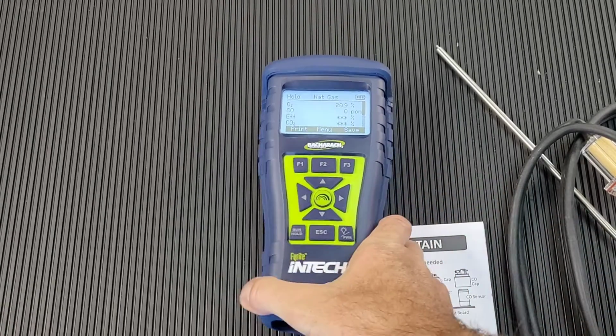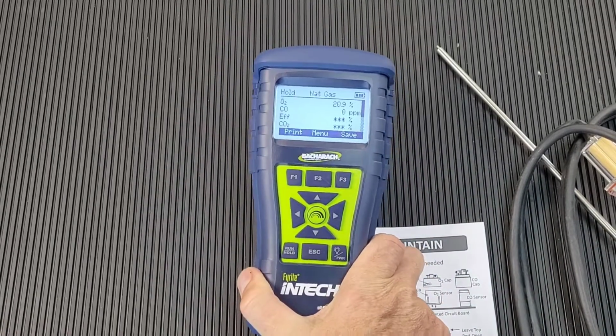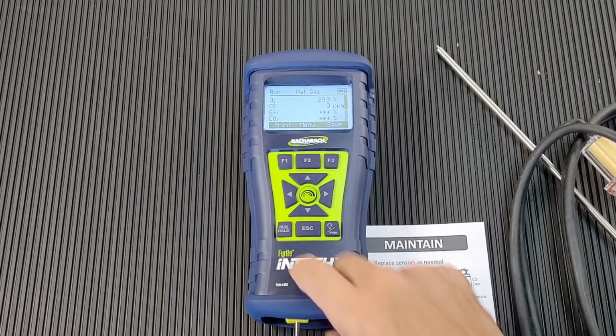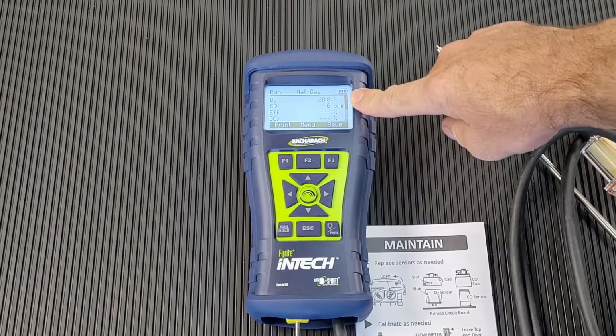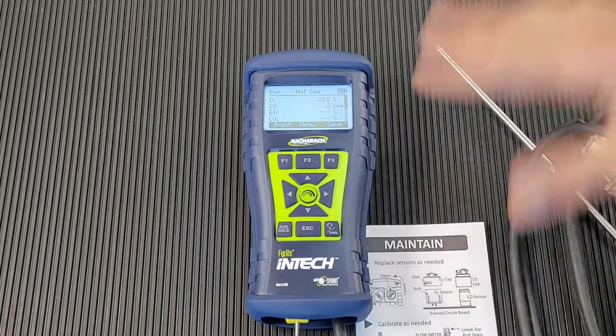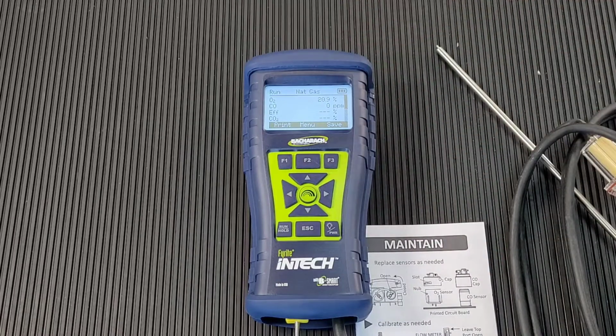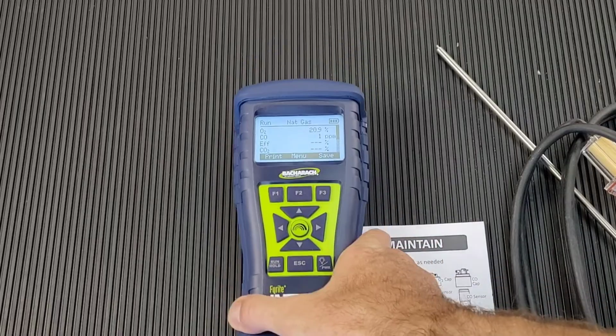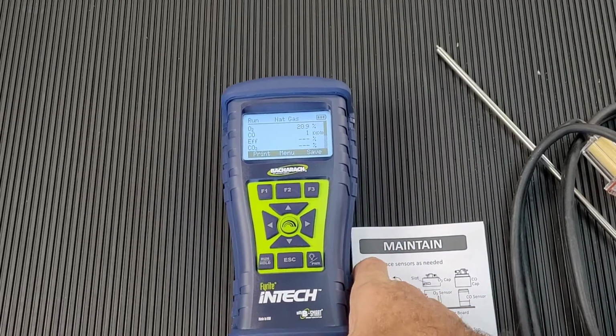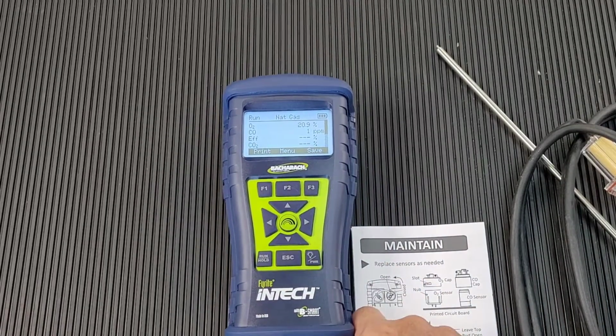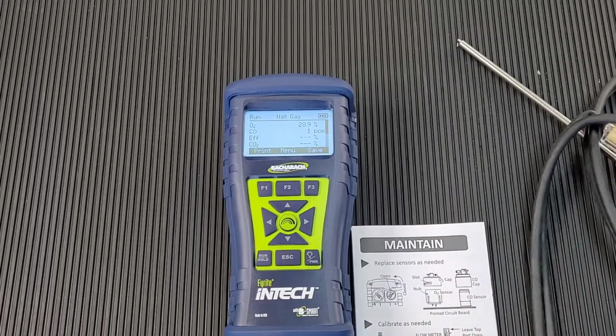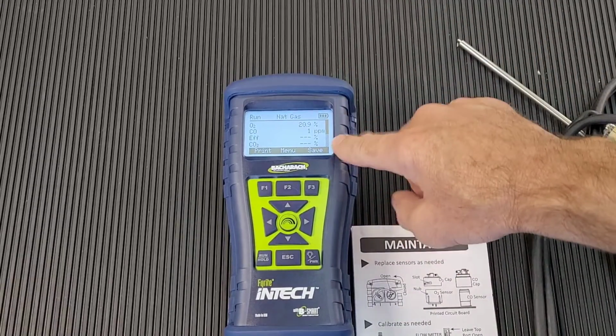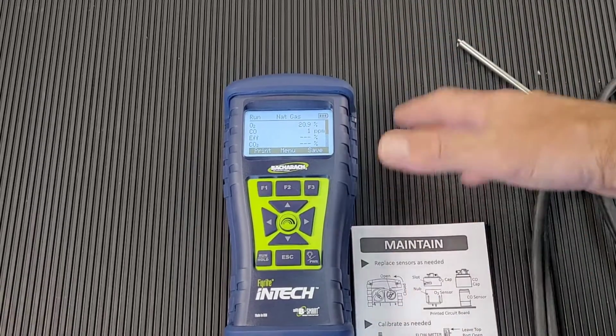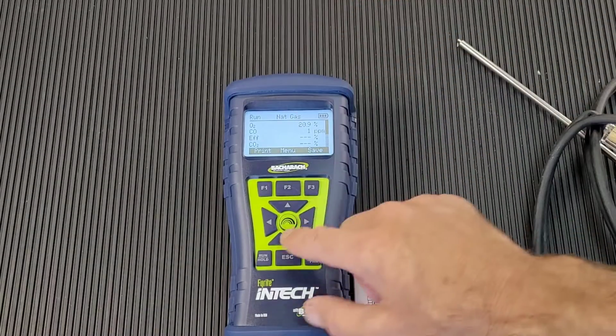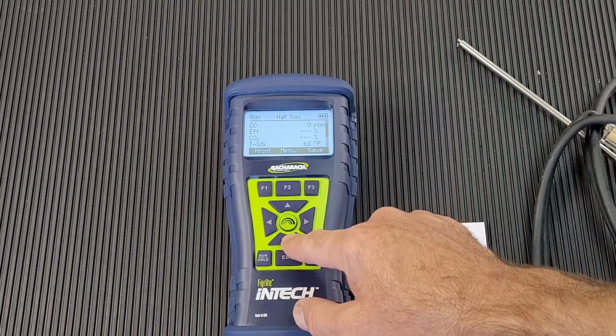Okay, good. This is good news. So we're back in the main display screen. I'm going to run the pump here. But the nice thing is 20.9, 20.8, even after 15 months, the oxygen is still very good. I think there's an auto calibrate when it does power up. So it's always going to read 20.9, which is very nice. And, you know, again, even my personal unit sort of fluctuates from 0, 1 or 2 ppm, and that's very normal on these units, okay?